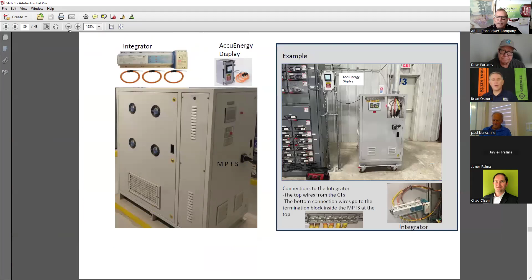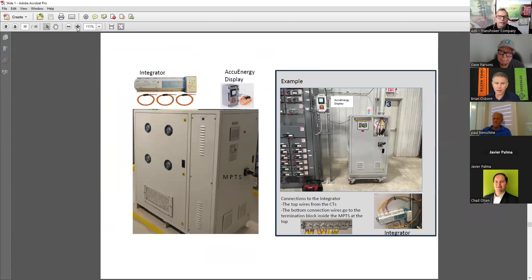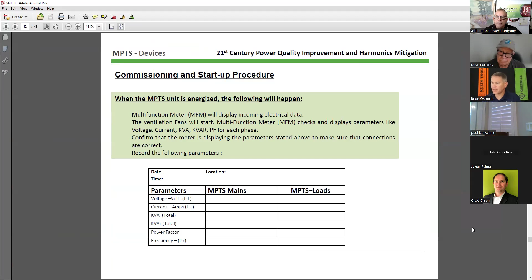What other problems can I think of? What about environmental problems? A lot of manufacturing will have lots of dust and debris floating around in the air. I can tell that is a NEMA 1 enclosure, so it needs to be provided with a pretty dust-free environment upon installation. Actually, if you have just regular dust, or just dust particles flying around, I've not had a dust issue anywhere that created a problem. Dust, from an engineering point of view, is actually a good insulator as long as it does not have minerals in it, because dust particles that are flying around usually don't have minerals.